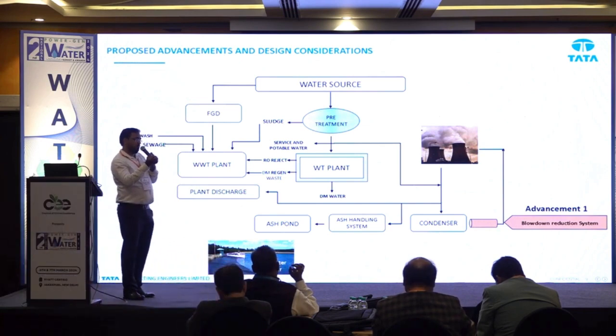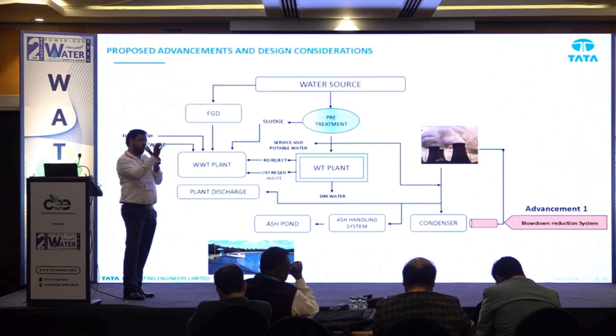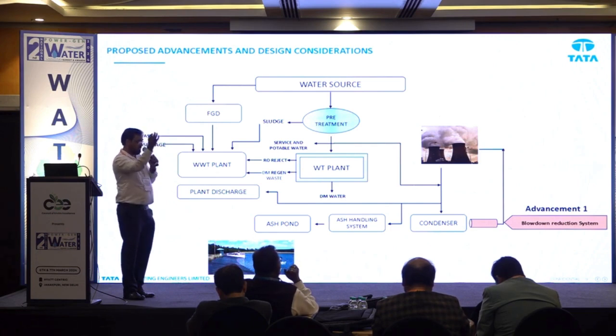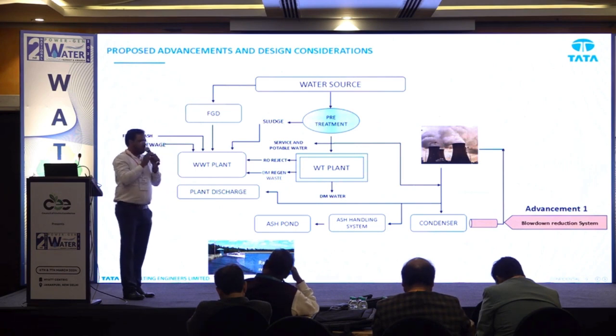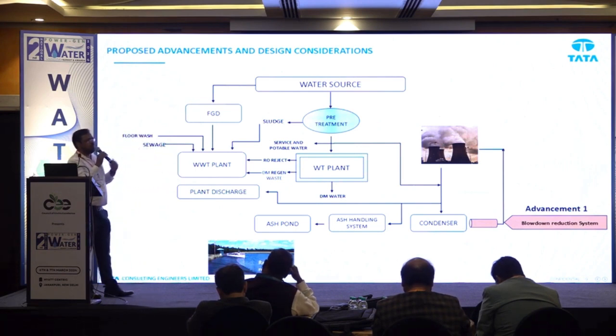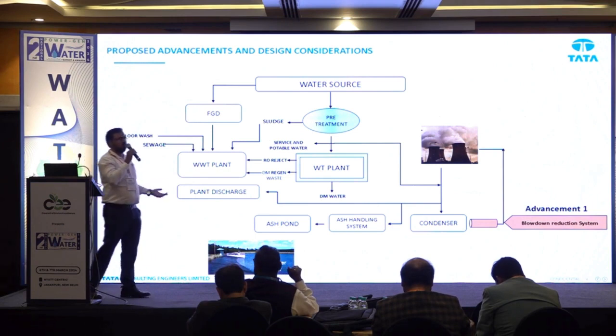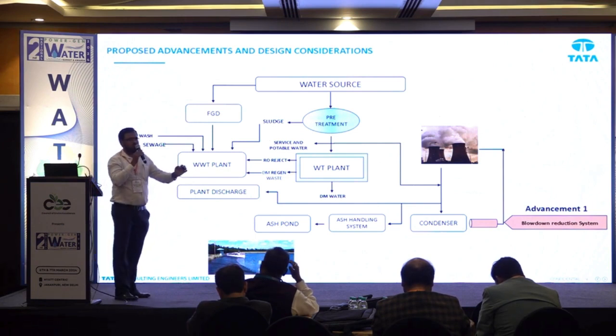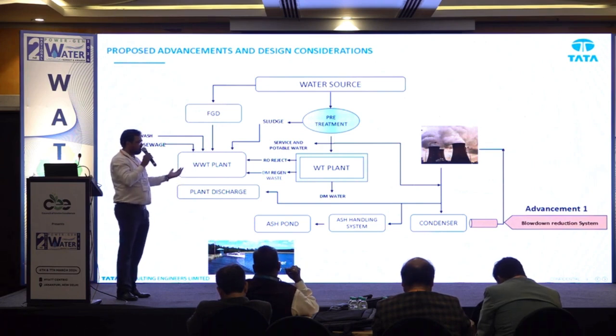And inside the equipment there will be turbulent flow at high speed. So the calcium and magnesium will not precipitate as scale; instead they become colloidal particles, and won't get stuck inside the condenser - they will pass through at high speed and come out. In this way, blow-down COC can be increased to a level of 5 to 6 to 7.